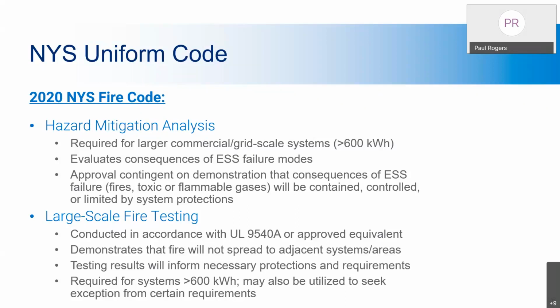It's required for systems more than 600 kilowatt hours — that's the maximum threshold for lithium ion in the code itself. For other chemistries there are slight differences, but for lithium ion it's 600 kilowatt hours. You may be able to go higher if you get that large scale testing done. I've noticed a lot of people doing that large scale testing and bringing results to the AHJ so they feel safe that the system can go into their jurisdiction, whether indoors, outdoors, or whatever the case may be.